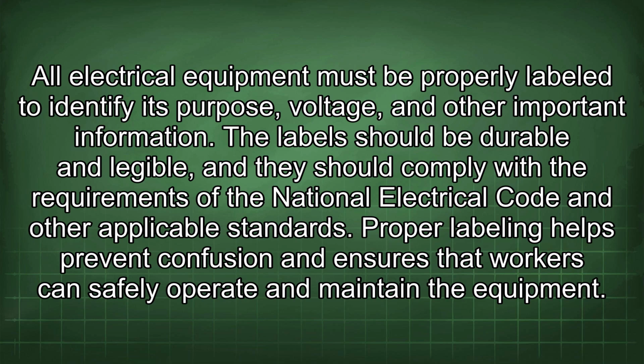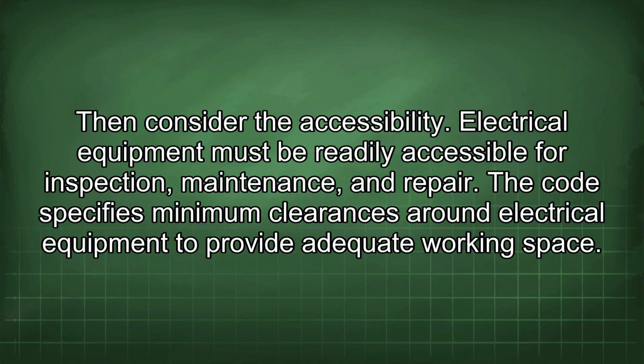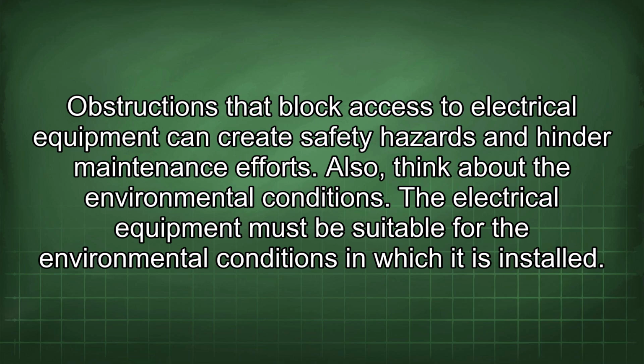All electrical equipment must be properly labeled to identify its purpose, voltage, and other important information. The labels should be durable and legible, and they should comply with the requirements of the National Electrical Code and other applicable standards. Proper labeling helps prevent confusion and ensures that workers can safely operate and maintain the equipment. Then consider the accessibility. Electrical equipment must be readily accessible for inspection, maintenance, and repair. The code specifies minimum clearances around electrical equipment to provide adequate working space. Obstructions that block access to electrical equipment can create safety hazards and hinder maintenance efforts.